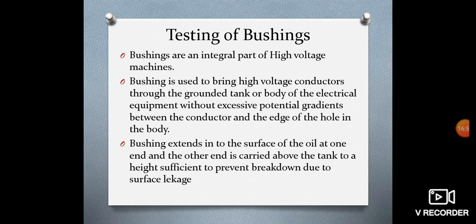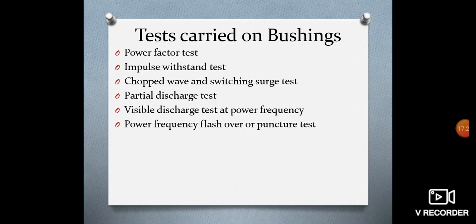So next part, we'll understand about testing of bushings. Bushings are an integral part of high voltage machines. A bushing is used to bring high voltage conductors through the grounded tank or body of the electrical equipment without excessive potential gradients between the conductor and the edge of the hole in the body. The bushing extends into the surface of the oil at one end, and the other end is carried above the tank to a height sufficient to prevent breakdown due to surface leakage.